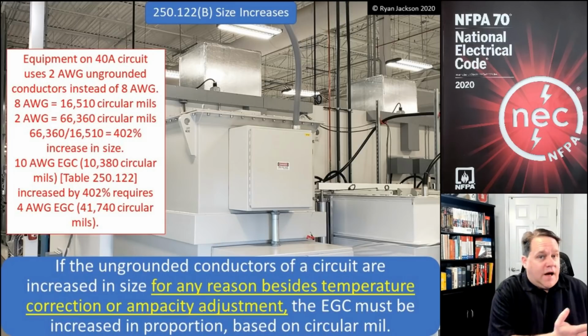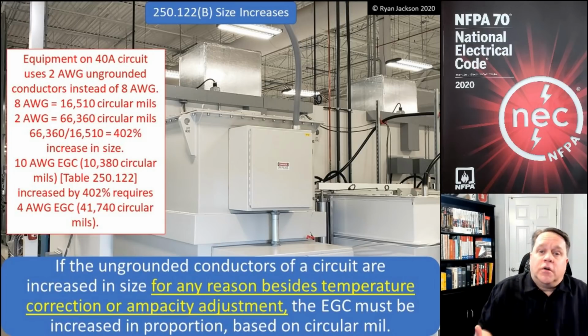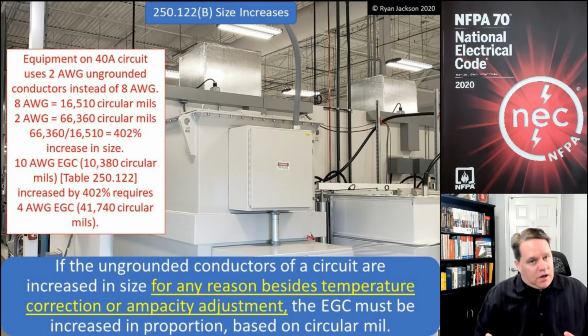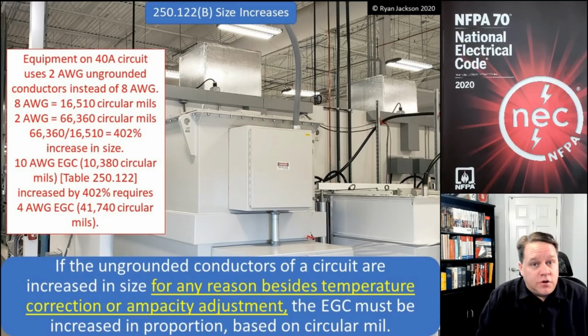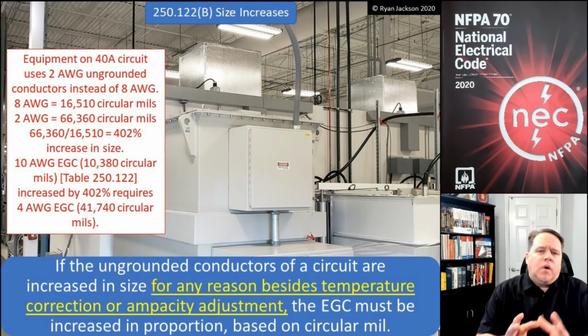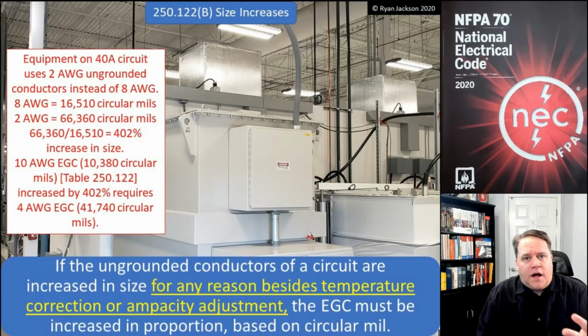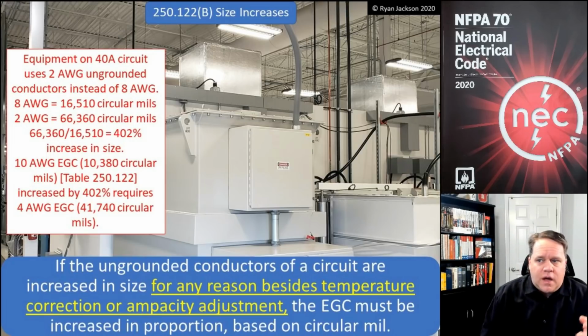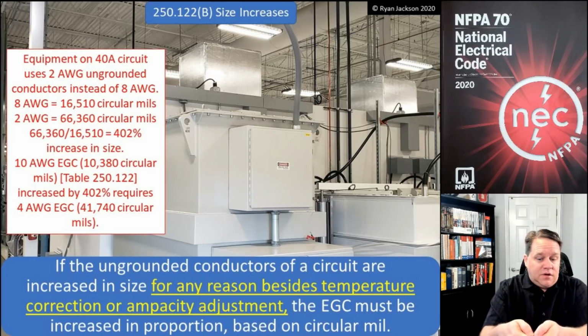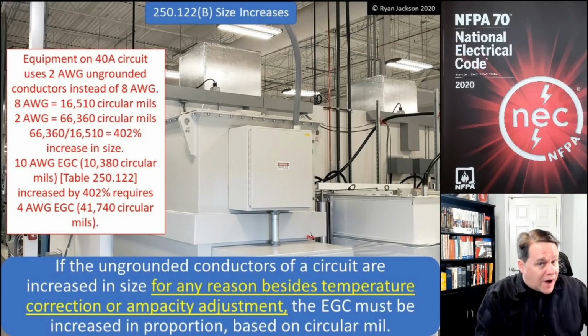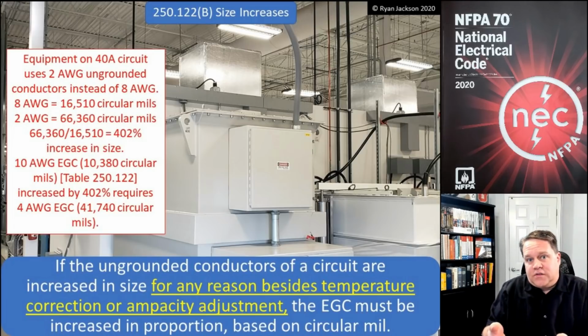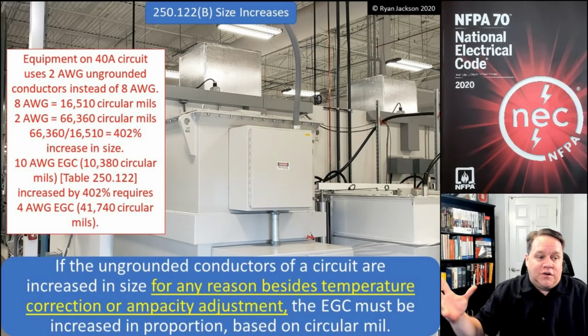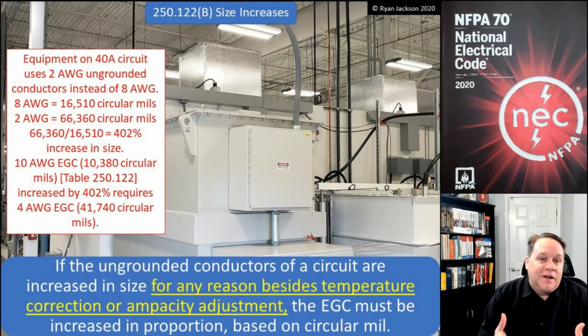We want breakers to trip faster and fuses to open faster during a fault, so there's nothing wrong with that, right? Well, to a certain extent, that's true. But how far can we get carried away here? What happens if I have like a 4-aught ungrounded conductor and I use a 12 gauge equipment grounding conductor? When I hit those two together, is the breaker going to trip? Well, probably, but there's also a decent chance that that 12 gauge copper conductor turns into molten copper. It's going to evaporate because of how much current it's subjected to for that short duration.